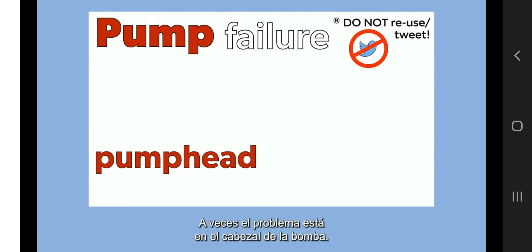This is because centrifugal pumps are non-occlusive, and when a centrifugal pump stops, you risk a phenomenon named backflow, with blood from the return cannula and return line flowing reversely through the system, contributing to hemodynamic derangement. So do not forget to clamp the return line until the issue is detected and solved, and RPM can be increased again. Sometimes the problem is in the pump head.